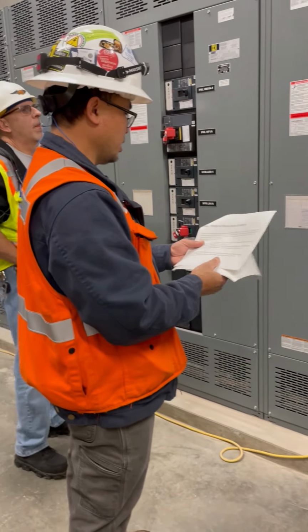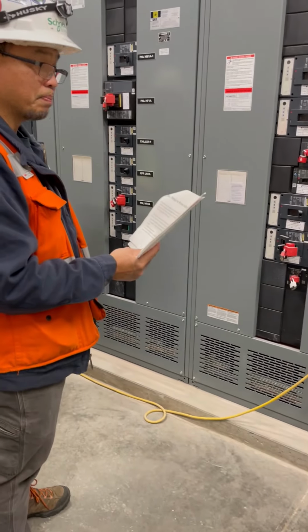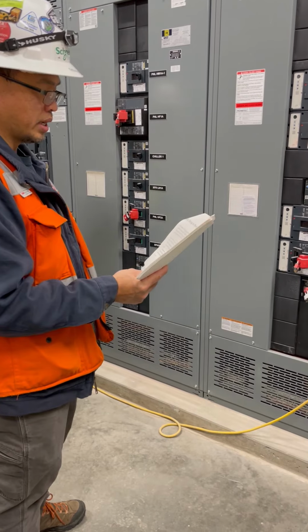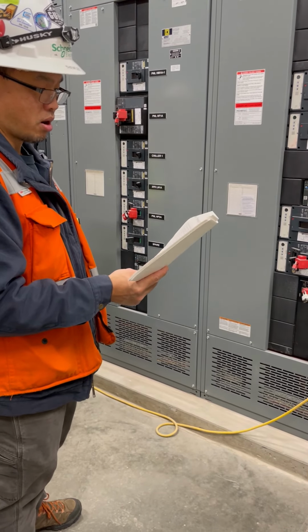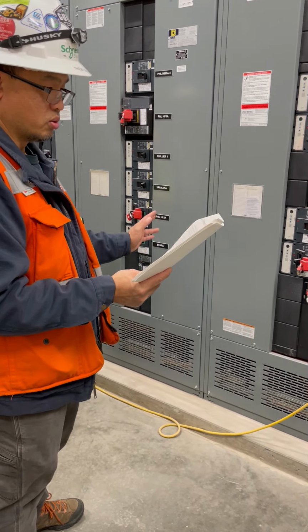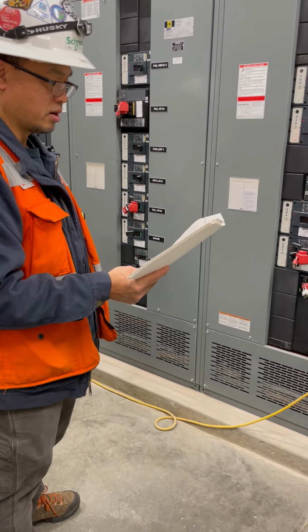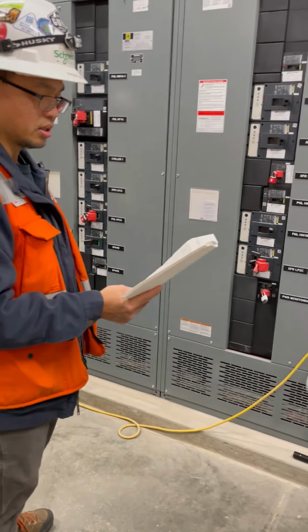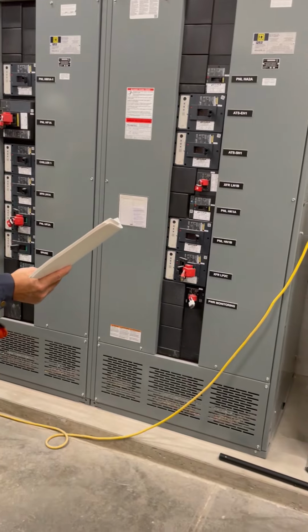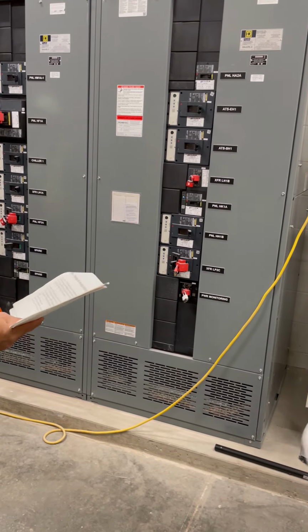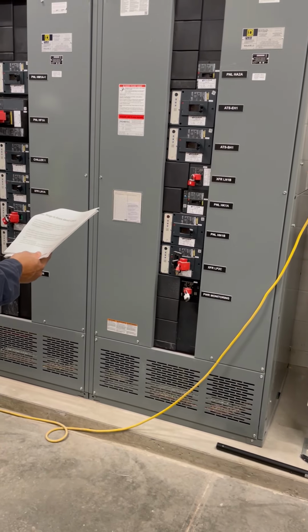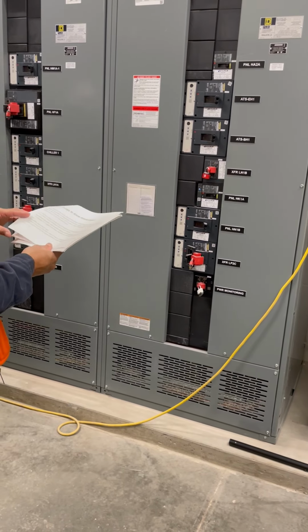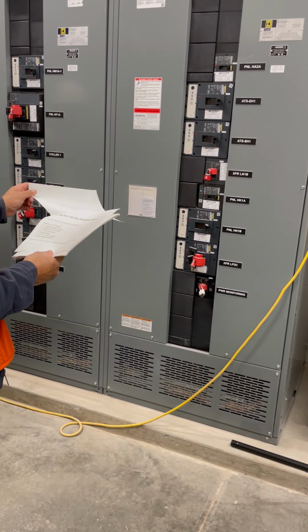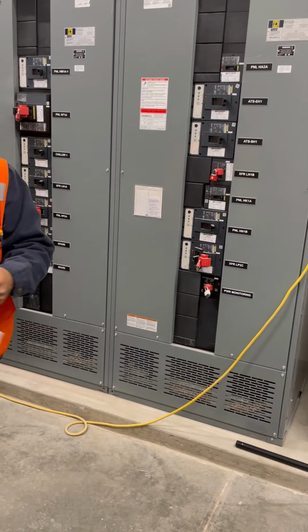The value in the study and on the label shows the incident energy expected when a worker is exposed to energized conductors or parts. There's no calculation that we can do when the covers are in place, doors closed, etc. The science of arc flash is not that advanced. I think that's about it for my portion.